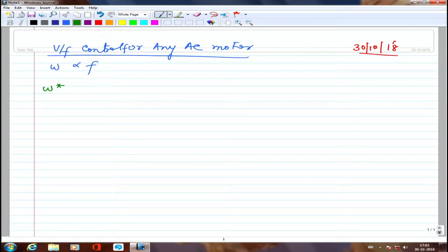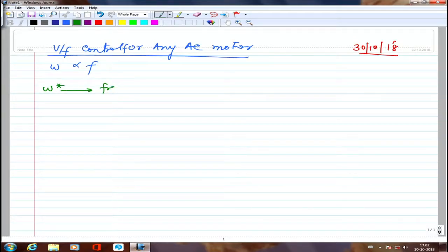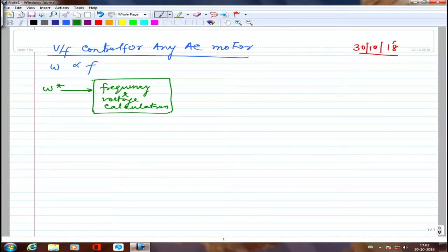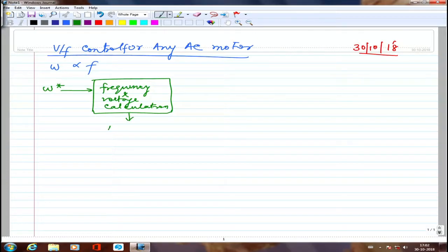Because we want to operate at constant flux, we assume E/F equals V/F. So if I want a particular speed, first I calculate the frequency, and correspondingly I calculate the voltage. Frequency and voltage calculation can be done based on whatever speed I want. Once I calculate the voltage, I can calculate the modulation index — that is, the amplitude modulation index — directly.